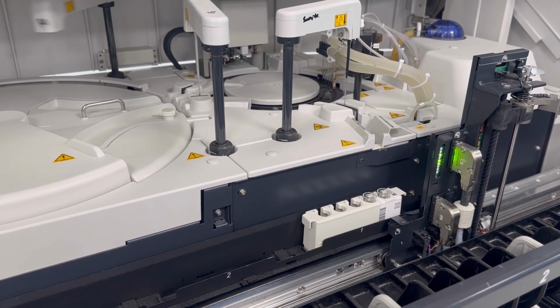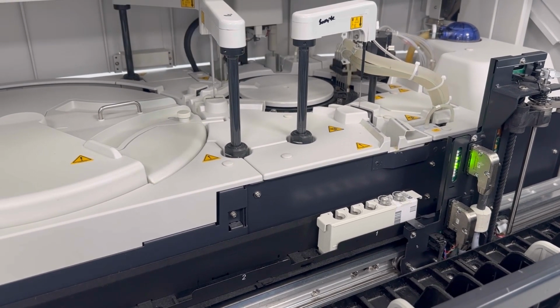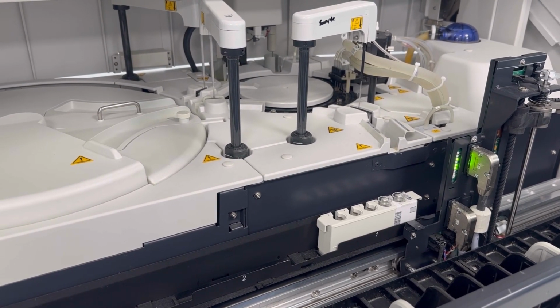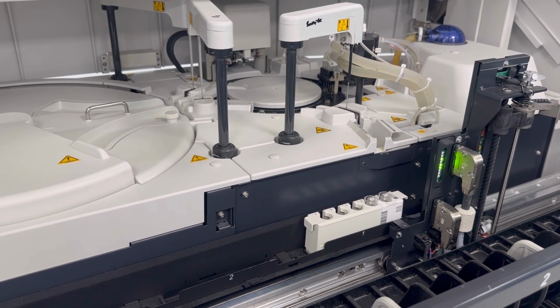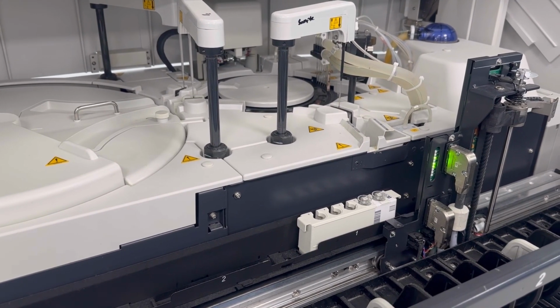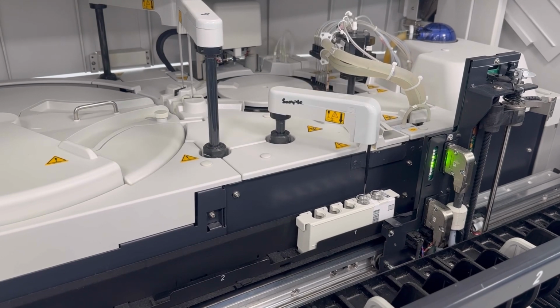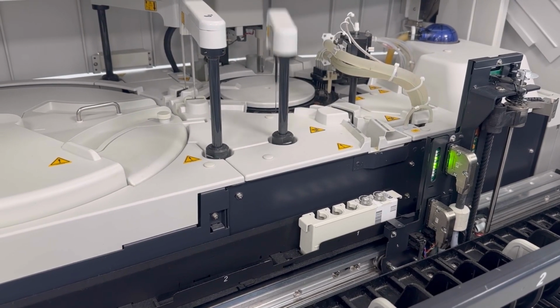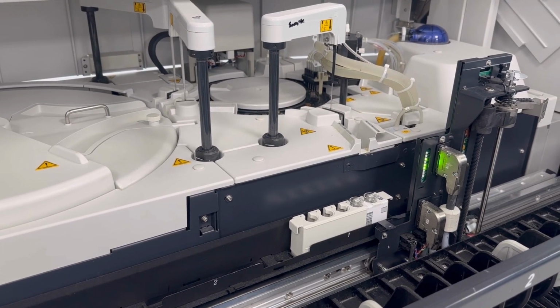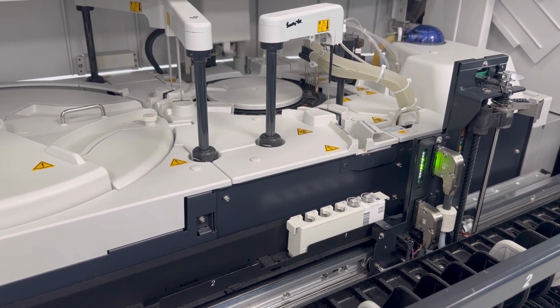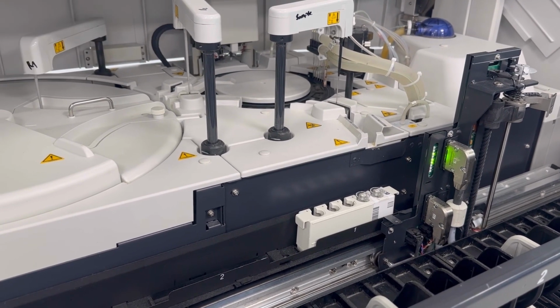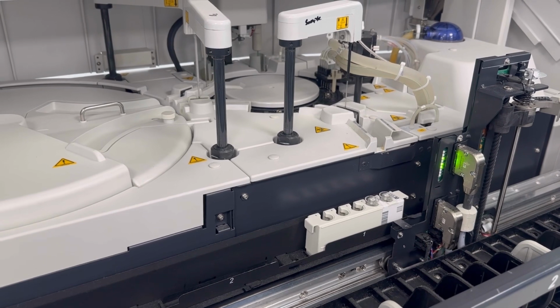As you can see the probe, and for this probe also, friends, it should be in very good condition. Make sure that whenever you keep the sample here in the machine, it should not have fibrinogen. I have already discussed this fibrinogen in my stories on Insta. If you follow me on Insta, you can see that. If you have fibrinogen, the probe cannot aspirate the serum from it.